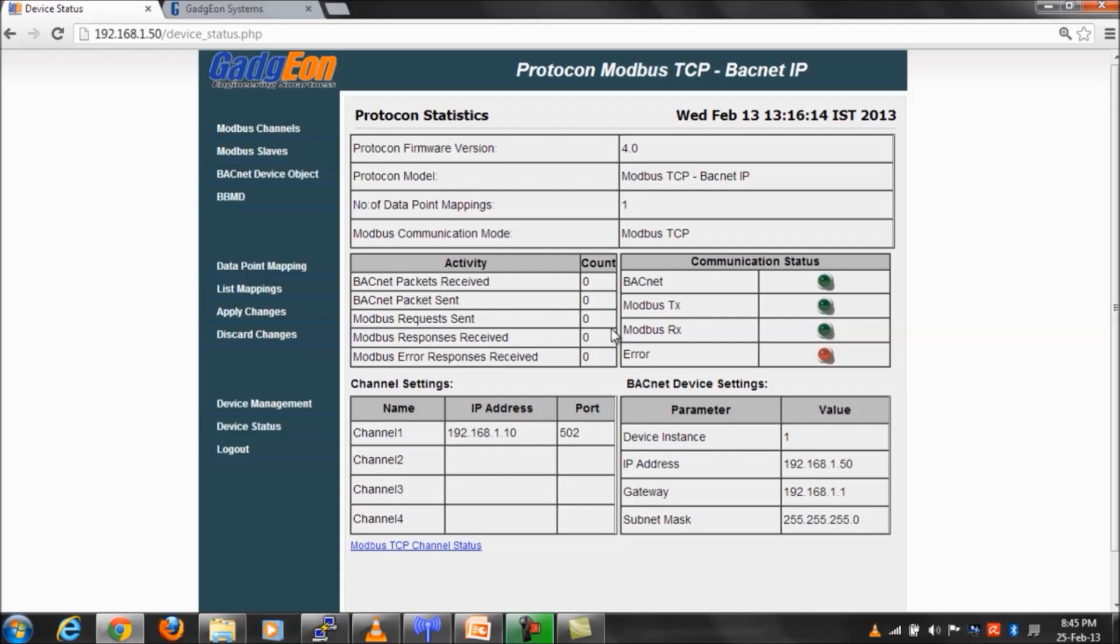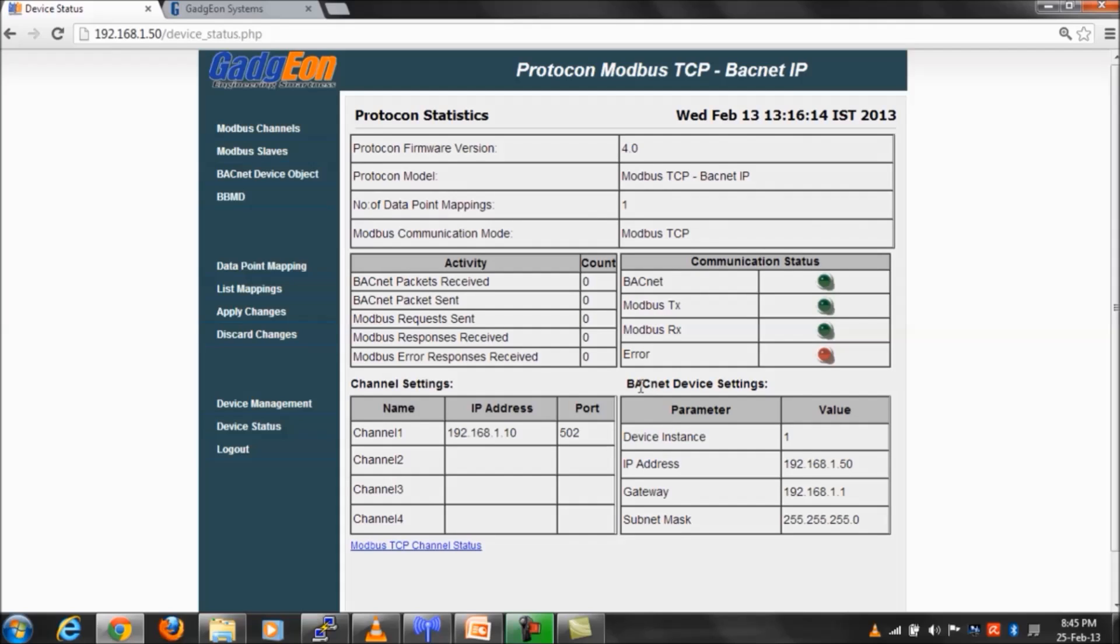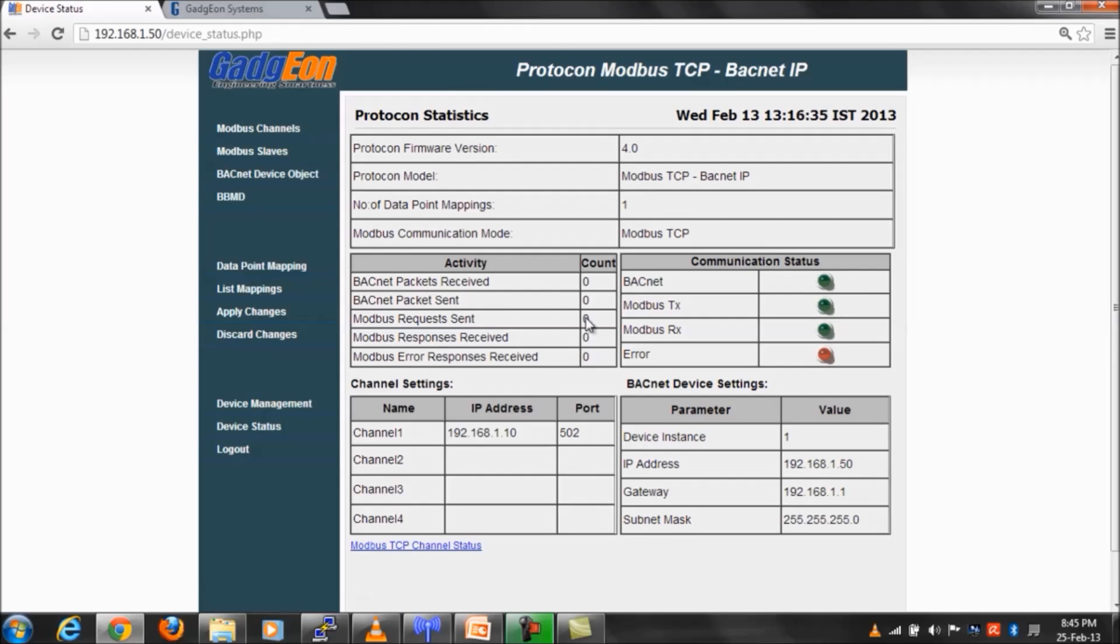This status page is automatically updated every 5 seconds. We have tested the gateway functionality specific to Modbus and Bacnet, as well as the WebGUI interface, using automation framework Robot Framework in an incremental integration and release manner.